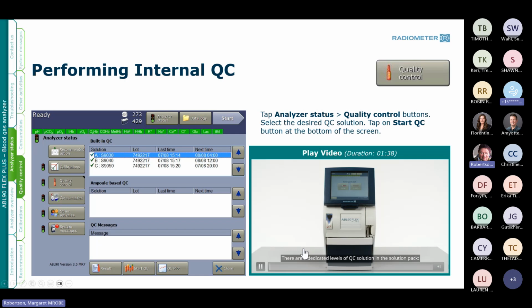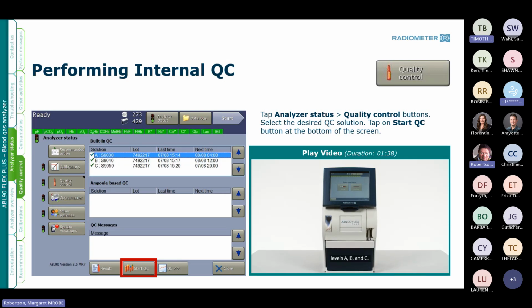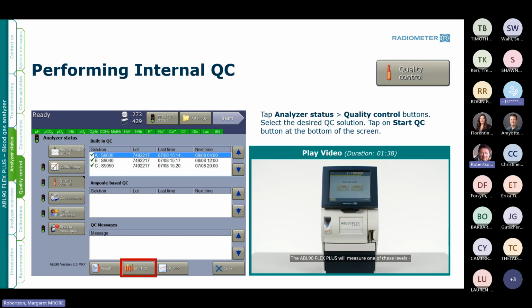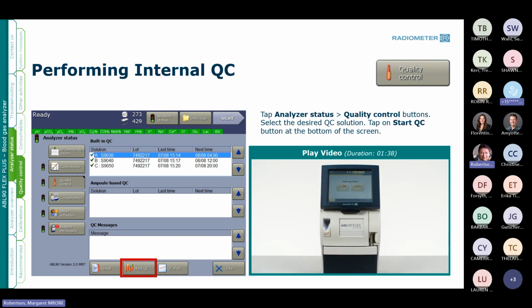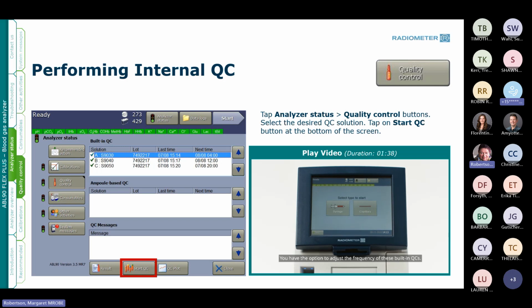There are 3 dedicated levels of QC solution in the solution pack. Levels A, B, and C. The ABL90 Flex Plus will measure one of these levels every 8 hours by default. You have the option to adjust the frequency of these built-in QCs.